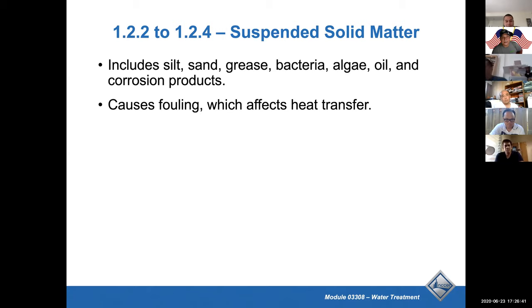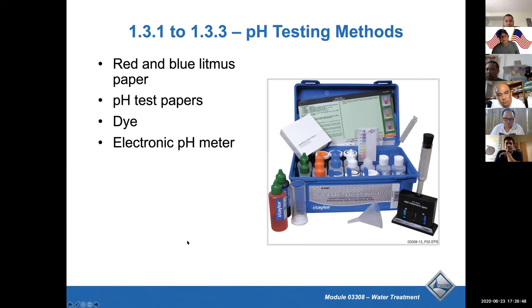Suspended solids include silt, sand, grease, bacteria, algae, oil, and corrosion. Solids affect heat transfer. Okay. Here's some ways to test pH with litmus paper, with red and blue litmus paper, which changes color when you put it up against the scale. Okay, pH test papers, which you also use a scale. See this little drawing, this little color scale here? That tells you what pH is. There's a dye, and then you can get an electronic pH meter, which I don't see here.